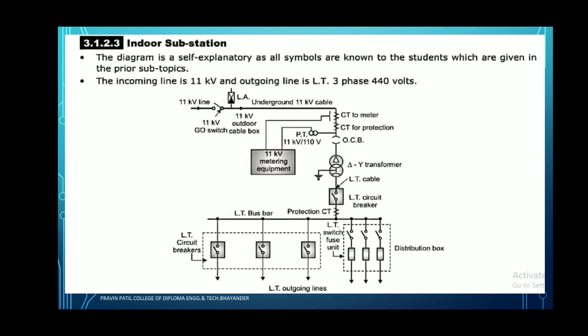Next, indoor substation. This is the diagram representation for the indoor substation. It consists of the lightning arrestor. Here the 11 kV line directly feeds the first lightning arrestor. Near that lightning arrestor, the transformer device is connected. So one terminal of the lightning arrestor is connected to the overhead line and the other terminal is directly connected to the switch and that source.